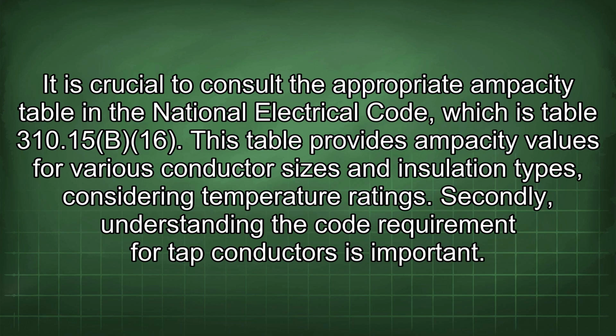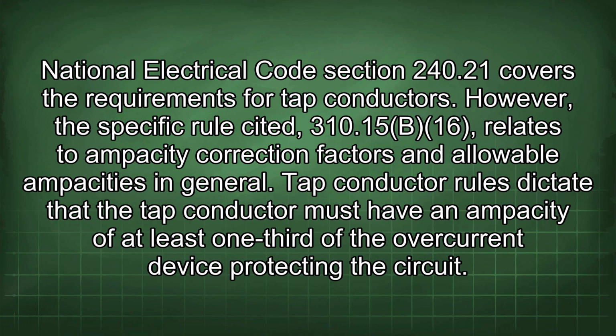Secondly, understanding the code requirement for tap conductors is important. National Electrical Code Section 240.21 covers the requirements for tap conductors. However, the specific rule cited, 310.15(B)(16), relates to ampacity correction factors and allowable ampacities in general.